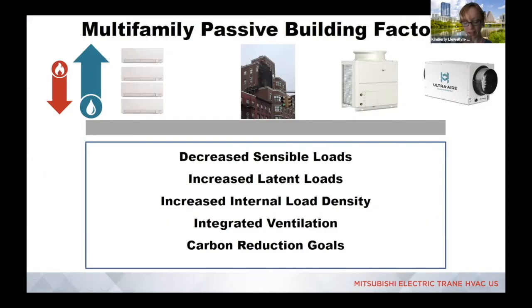So again, this is really to say we still have a lot to learn, but we understand the needs of passive buildings pretty well. We understand that you've been asking for lower capacity equipment for a long time. We share the same concerns as you about high GWP refrigerants. And we know that with our lower sensible load buildings we start seeing a reversal in sensible heat ratios in our spaces, which means that we have to do better with latent control of dehumidification.